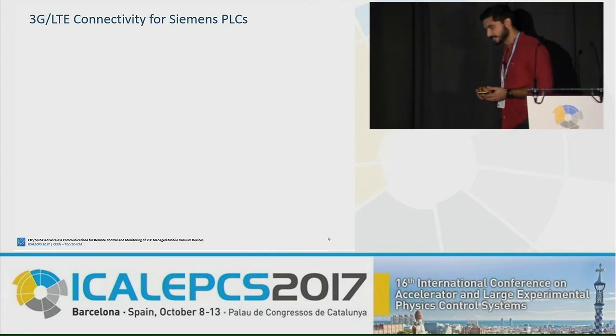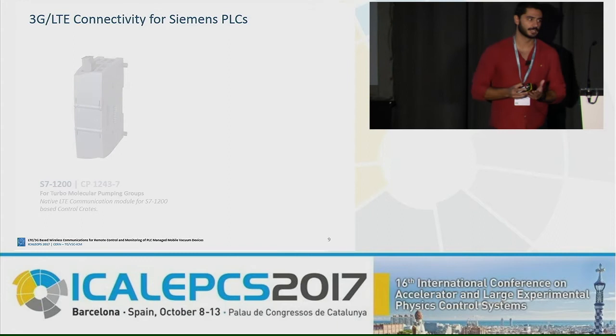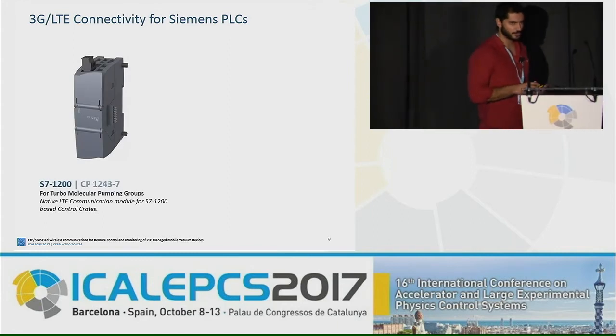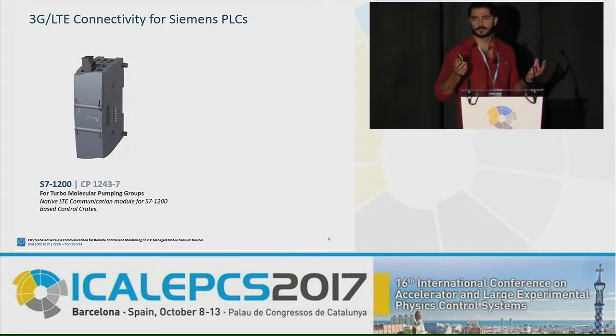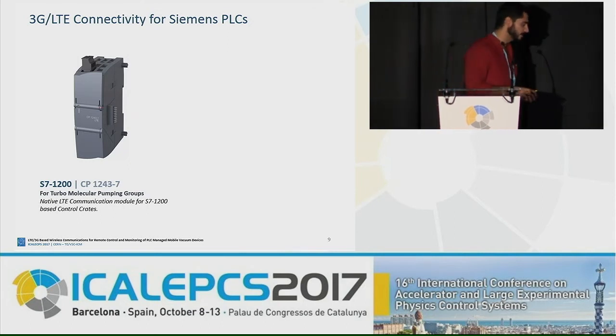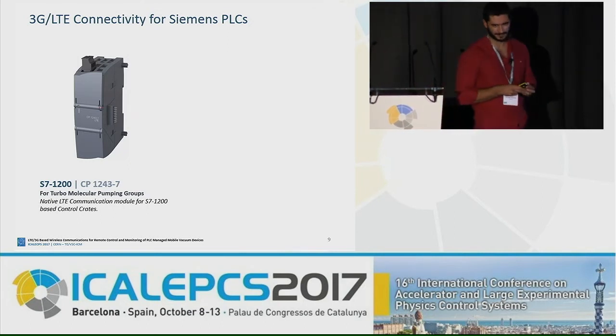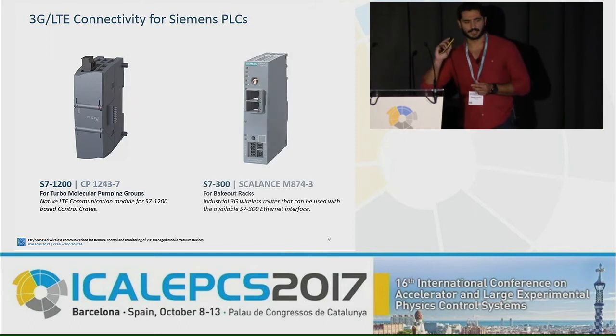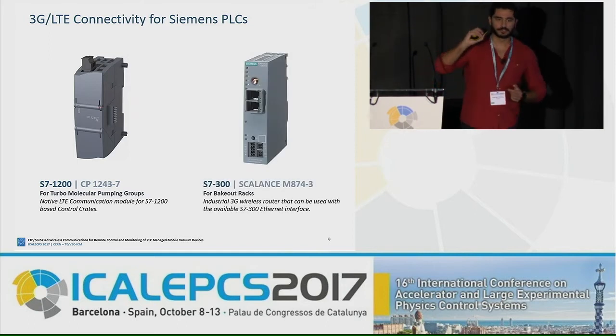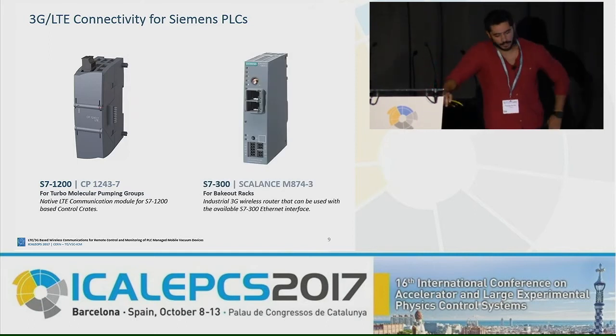Now that we decided to use GSM for our wireless system, we have to provide GSM connectivity for our PLCs. If you're using a Step 7 1200, you can do this natively, since Siemens has modules which provide native connectivity for GSM. But this is not the case for the Step 7 300, which is an older ecosystem, so we have to use the Ethernet port.